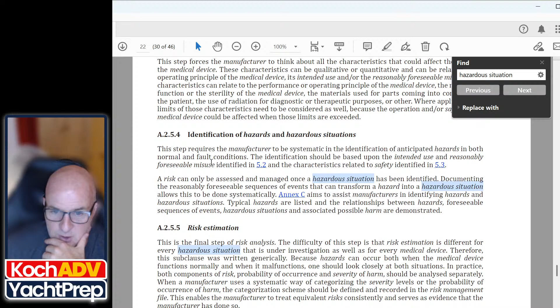So the hazardous situation should be based on the intended use, reasonably foreseeable misuse, and the characteristics related to safety. Risk can only be assessed and managed once the hazardous situation has been identified.